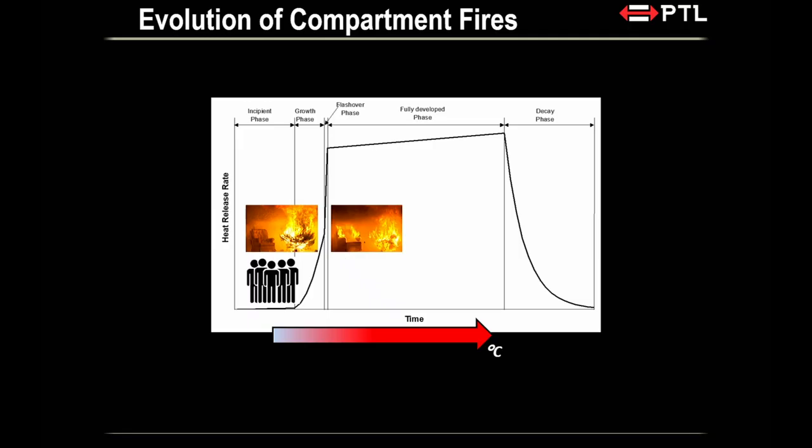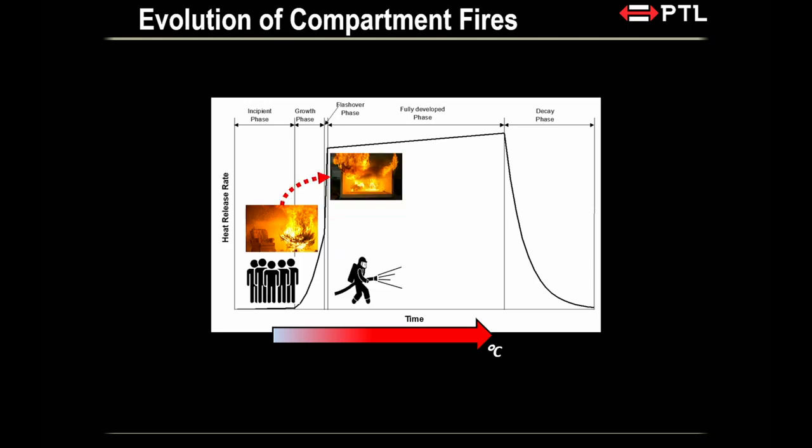Because very soon, you get into the short phase that we call flashover. What is flashover? Flashover basically means that any fuel that will burn inside a compartment will ignite at that point in time. So you will see that the fire size obviously goes up quite rapidly.